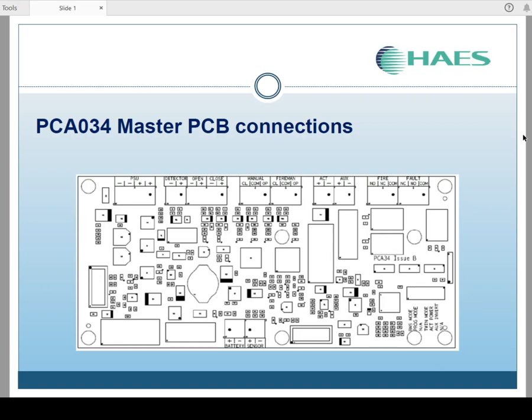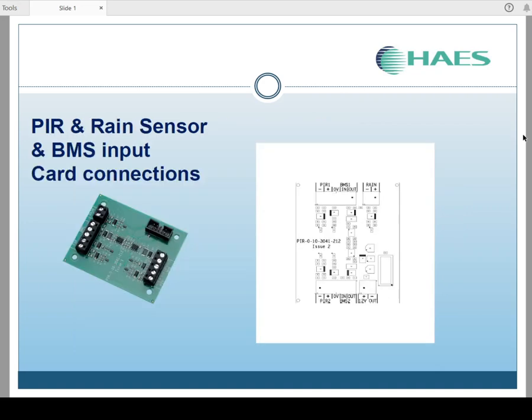And two relays to the right hand end, one fire and one fault, clean contacts, usable for many purposes. Going to the bottom edge, we have our battery input, pos and neg, our sensor input, pos and neg, temperature control. And to the right hand at the bottom there, there's a row of DIL switches that we'll run through in more detail, where you can make some quick changes to the operation of the panel.